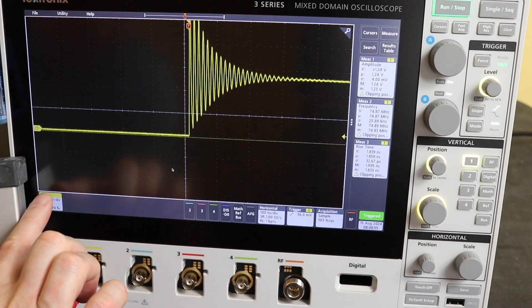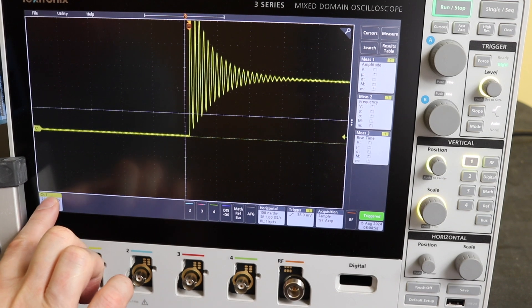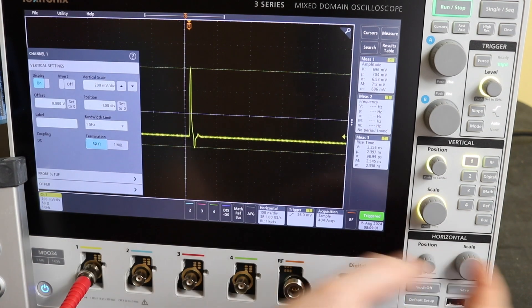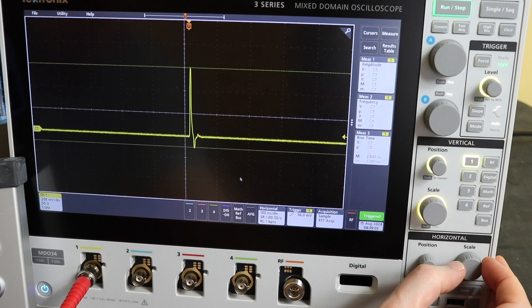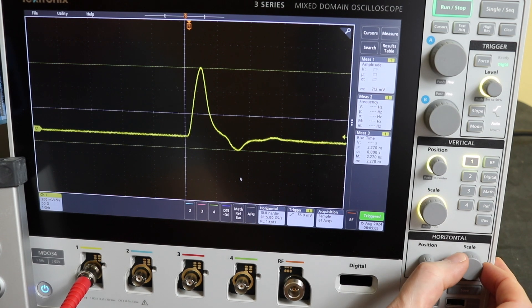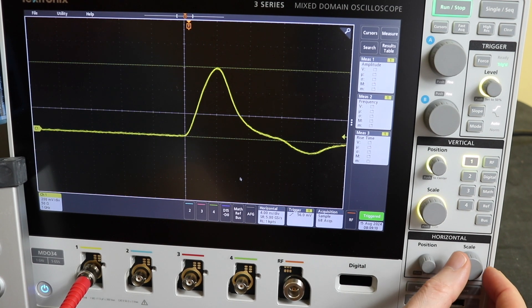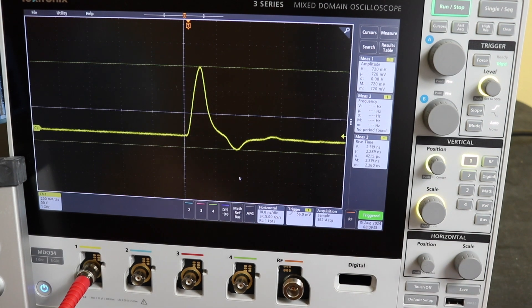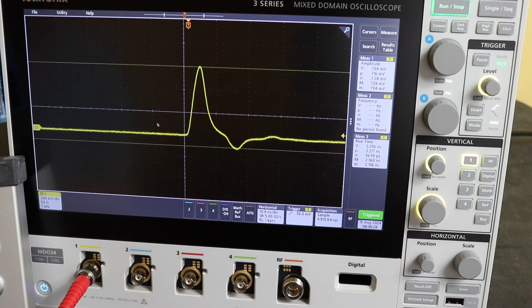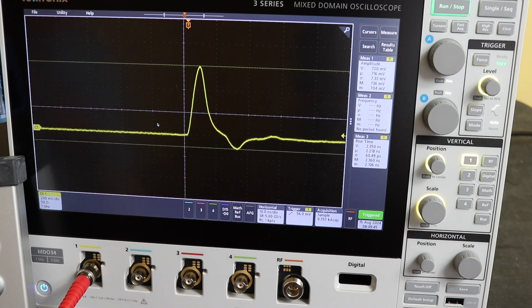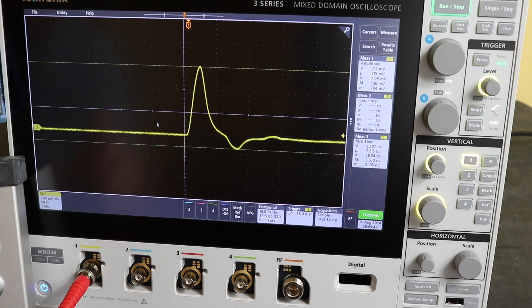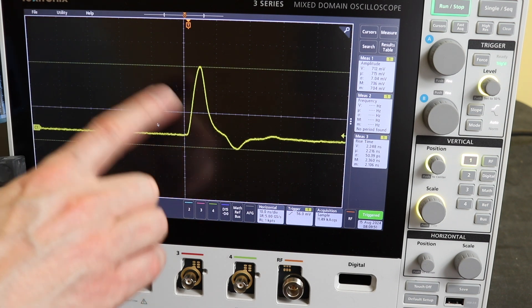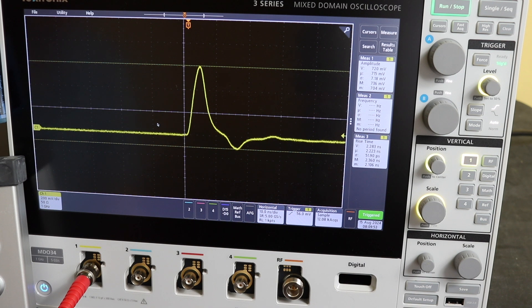What we can do is change the loading on the channel, put that down to 50 ohms and then we can get rid of that. Then scale them out a little bit more. There, you see, probably that's the best one there. You can see there that would be a typical partial discharge pulse if I was using the actual partial discharge acquisition equipment. That's the type of signal that would be seen if I zoom down to signal level, whereas in reality you've got thousands of these little pulses going on through an insulation system that the whole system picks up and analyzes.